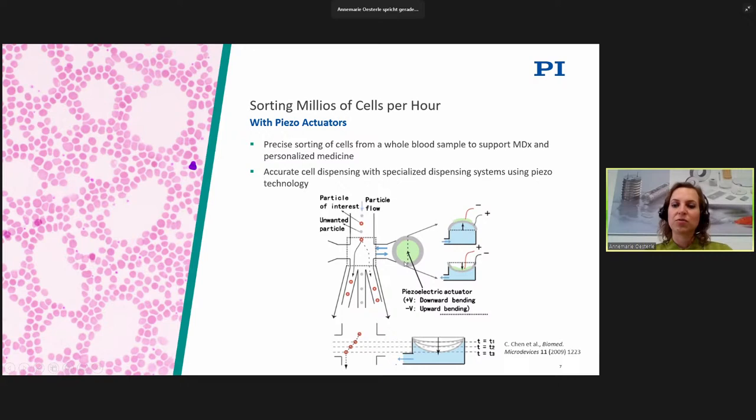So here, round piezo actuators are glued on top of this liquid chamber, and by applying a voltage, the actuator does a bending motion and therefore manipulates the liquid interface inside this cell sorting device. By expanding the actuator, the liquids are influenced and give a shock or a pressure pulse to the cells so that they kick them into one or the other channel in the sorting device.